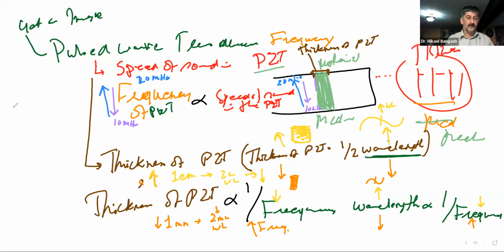And the best option for diagnostic imaging is a high frequency transducer. How do we get that? Primarily, it has to be a pulsed wave transducer. How do we get a pulsed wave transducer? We put some backing material in the transducer. That's going to make it a pulsed wave. But then we also use a material as the PZT which has a great speed of sound.